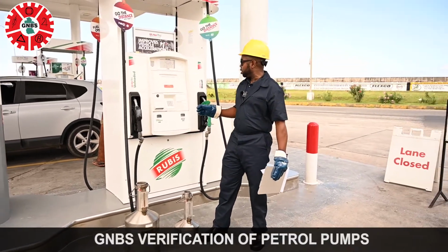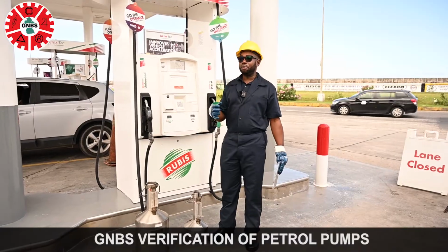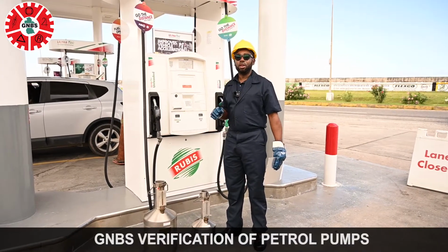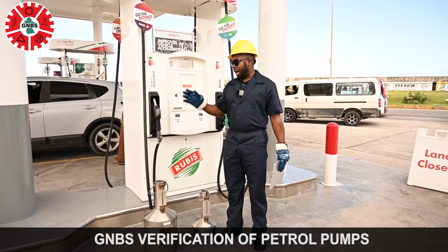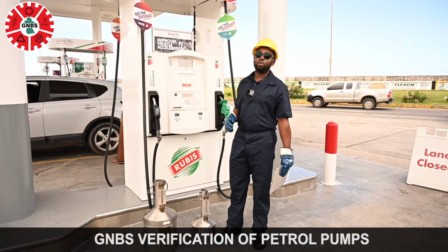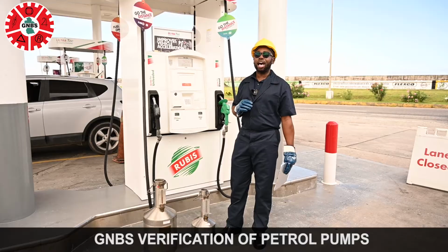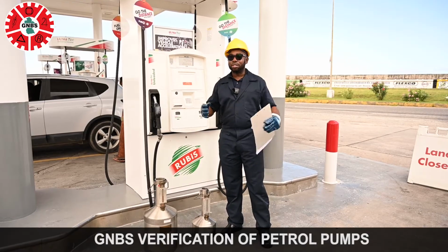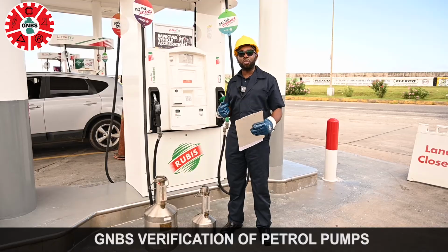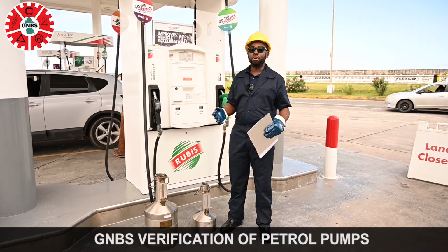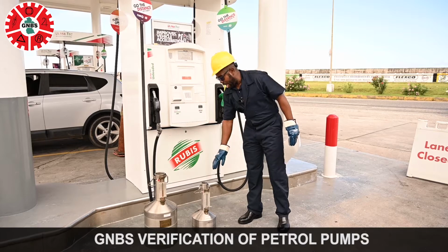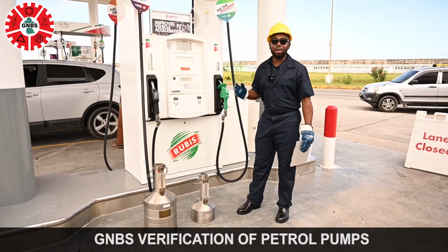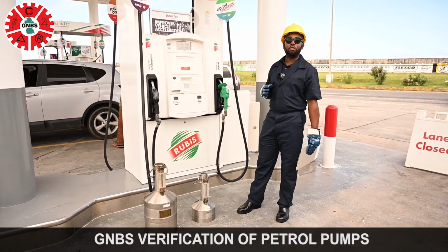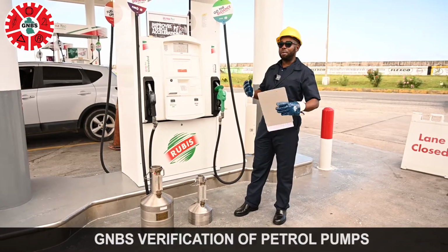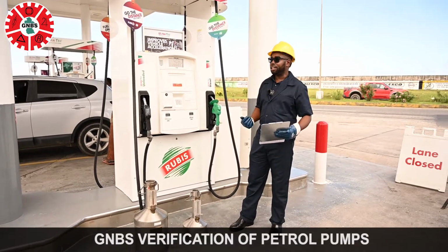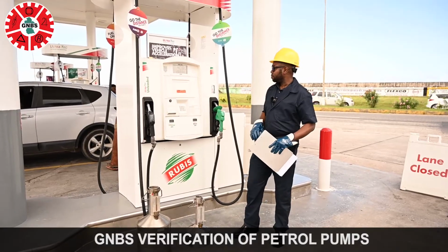In the verification process we run this test 3 times with the 20 liter measure: at a fast rate, as we just did, at a slow pace, and also a stop-start, which accommodates for when people purchase fuel if the meter stops and you continue. We'll also use a 5 liter test measure and do the same, running it 3 times slow, fast, start-stop, mimicking someone purchasing gas in large or small quantities.